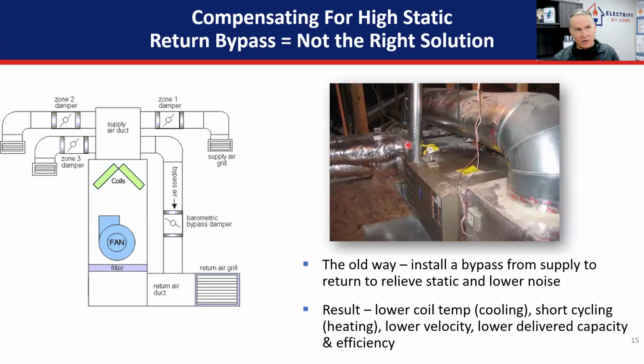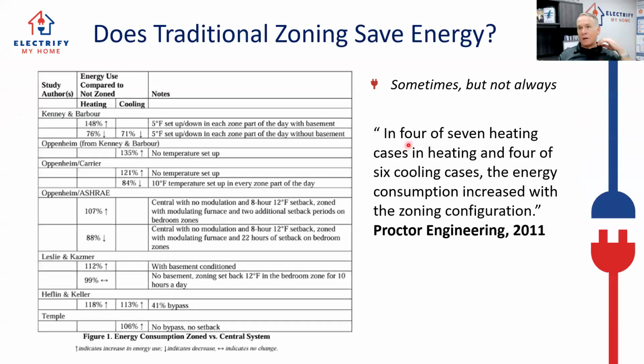And so what we see a lot of times is there's two-stage furnaces in the house, but there's not a two-stage air conditioner. So we're still blowing full capacity in cooling mode, but just not in heating mode. So you've got to think this stuff through when we do this and make sure that it's going to work for the customer. We need to put a system in that works, not just one that works for our commissions, right? So does it save energy?